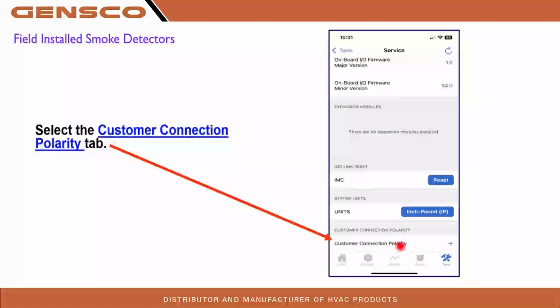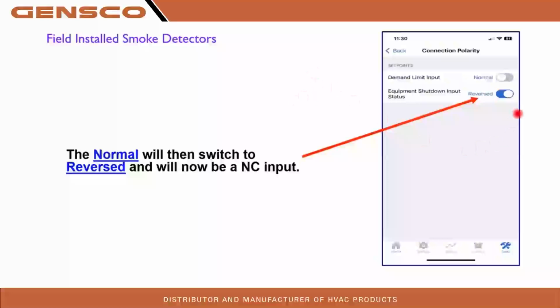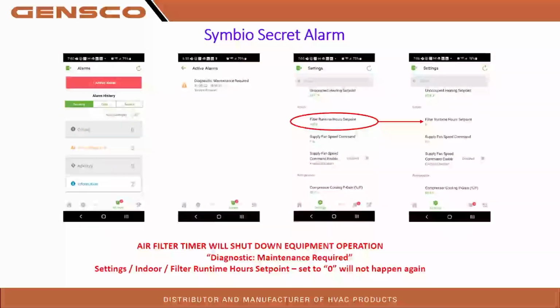Customer connection polarity, you're going to reverse it. So normal is normally open, reverse will be normally closed. So here's our equipment shutdown input status. Yeah, kind of a long way to get to that selection, but that's where it is. There's also a Symbio alarm, and it will shut down the system.